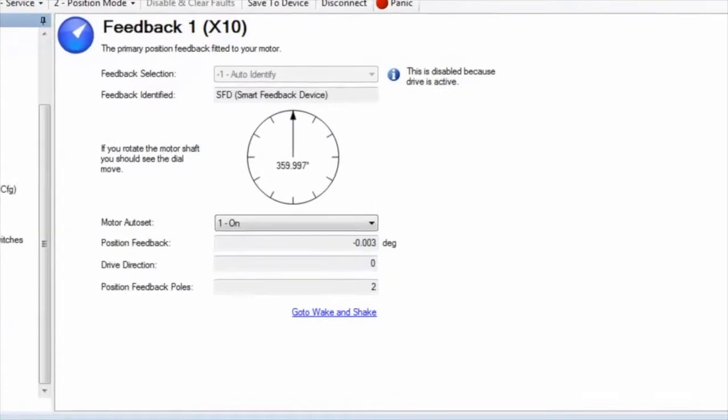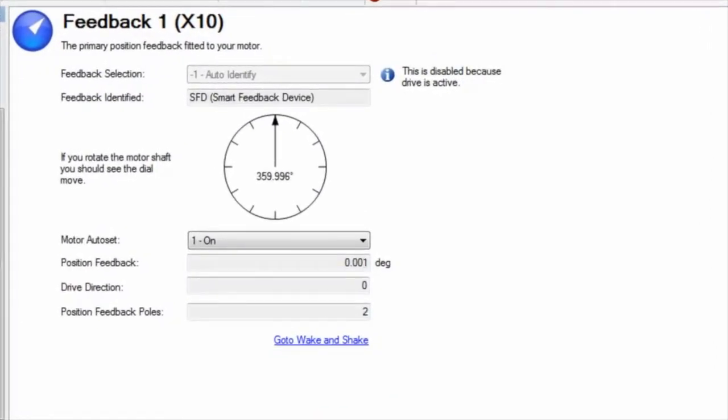If we start with the feedback device, we can wire it for clockwise rotation. When the machine is rotated clockwise, the position will count up. If it is counting down, swap A and A0 or B and B0 for a sine encoder or incremental encoder. For a resolver, swap sine and cosine.